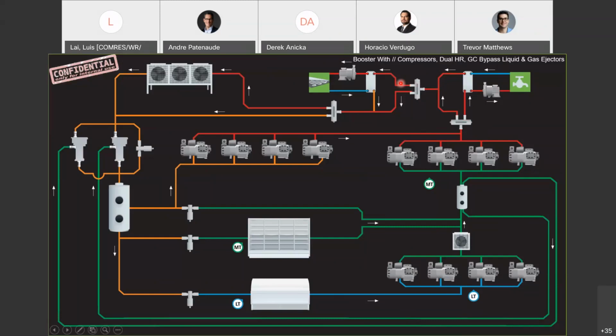And then if you have enough condensing going on in series, and this gas is condensed to a liquid or a low enough temperature gas, then it could be diverted to the high pressure valve without even going to the gas cooler. That's one option. Or it can move up to the gas cooler. There's some algorithms to do that. So we can do that with the iPro rack. That's one thing. We can manage parallel compression with the iPro rack.